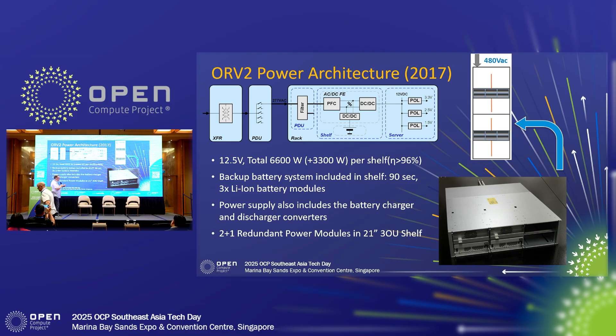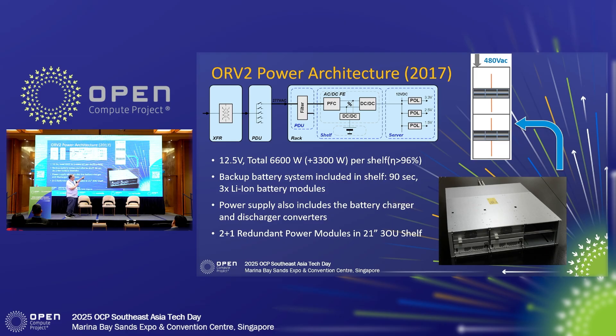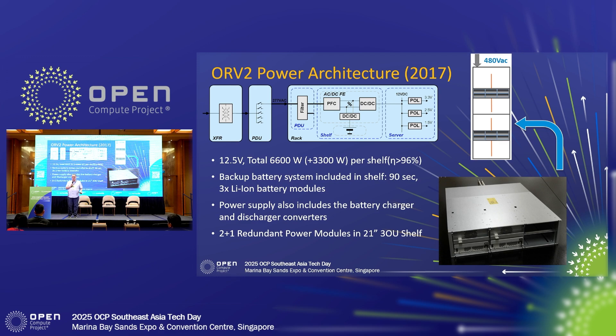In each one of those power shelves there's a rack-level BBU — one-to-one, a BBU module to the power supply in the ORV2. In the back it's got a solid bus bar, meaning there are holes in the bus bar with nuts and bolts that connect them together. This is ORV2, which has been around for quite a while and was very good. It puts out 12.5 volts because, as you may know, servers run on 12 volts.